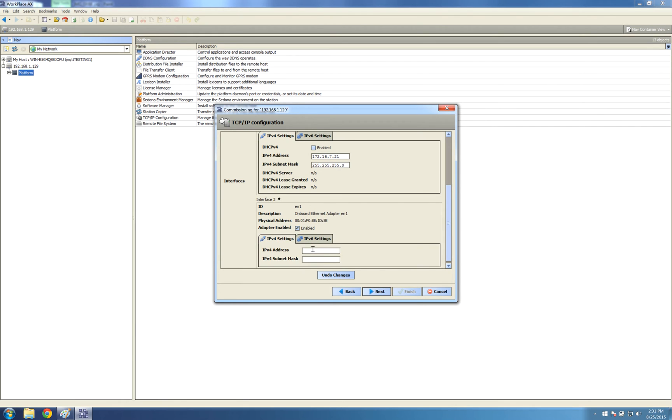Put in an IP address which is outside the range of my one that's on my primary port. You need to be completely out of the range of that. Otherwise, it won't work. The JACE will stop communicating.